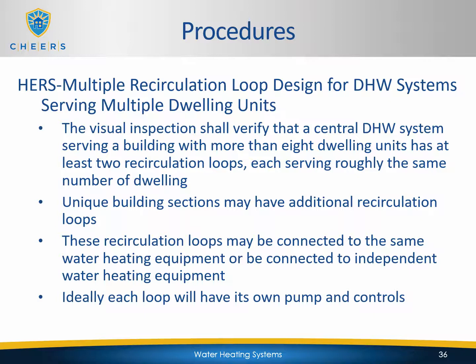For multiple recirculation loop design for domestic hot water systems serving multiple dwelling units, the visual inspection shall verify that a central domestic hot water system serving a building with more than 8 dwelling units has at least 2 recirculation loops, each serving roughly the same number of dwellings. Unique building sections may have additional recirculation loops. These recirculation loops may be connected to the same water heating equipment or to independent water heating equipment. Ideally, each loop will have its own pump and controls.